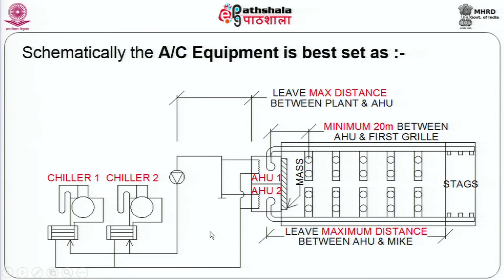So, in other words, if you are looking at a high rise building, consider putting all this equipment, which can be linked purely by two sets of pipes, on the rooftop or in the basement, which is quite far away from the air handling unit. Now, the air handling unit unfortunately cannot be shifted here, because the link between an air handling unit and an air conditioned space is very large. You need a large supply air duct and a large space for the return air duct. So, the moment you take this place away from the auditorium, establishing this link becomes very difficult, very expensive and very space consuming. So, very rarely does one try to take this equipment away.